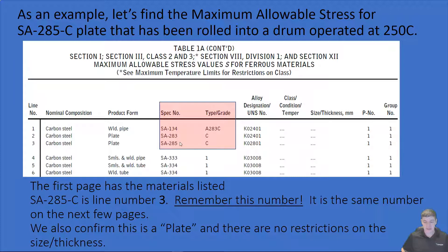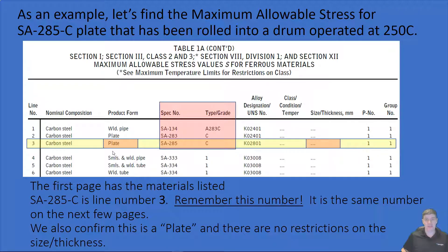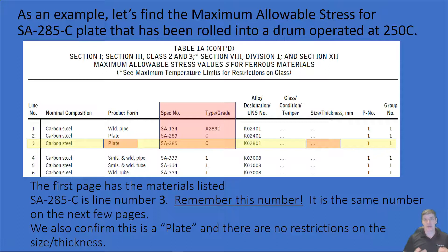Once you've found SA285C, do a couple of things. First, note the line number — in this case, line number three — because that carries over to all the subsequent pages. Then confirm this is the right application by checking the product form; it is a plate, so that makes sense. Also check size and thickness restrictions; some materials may only apply above a certain thickness, like 25 mm, but in this case there are no restrictions, so we move on.